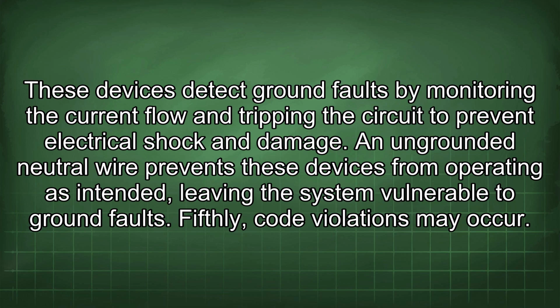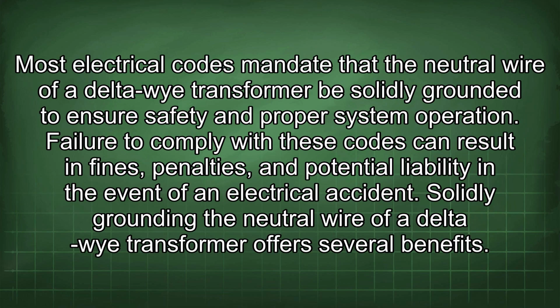Fifthly, code violations may occur. Most electrical codes mandate that the neutral wire of a delta-wye transformer be solidly grounded to ensure safety and proper system operation. Failure to comply with these codes can result in fines, penalties, and potential liability in the event of an electrical accident. Solidly grounding the neutral wire of a delta-wye transformer offers several benefits.